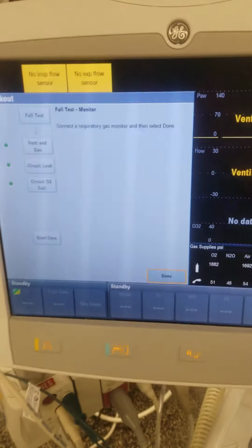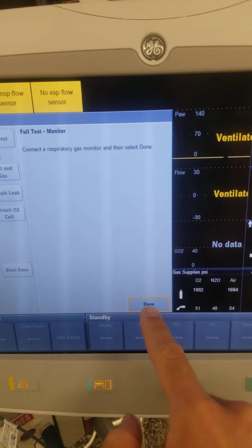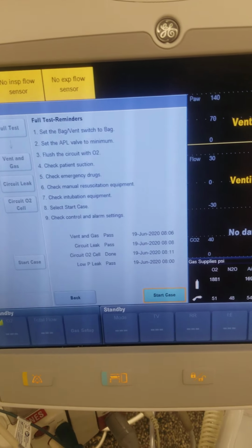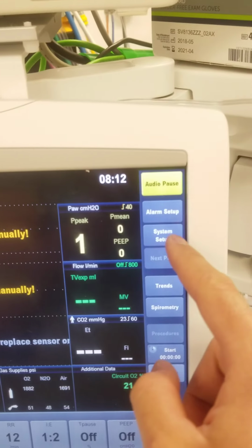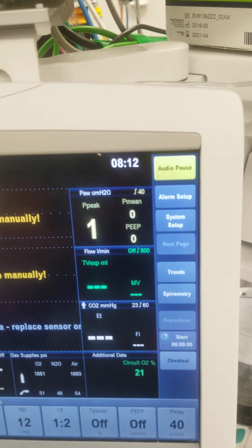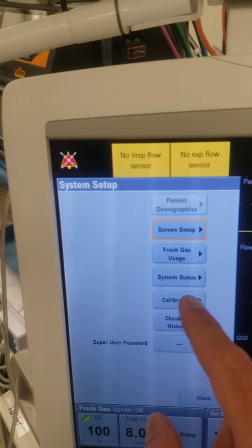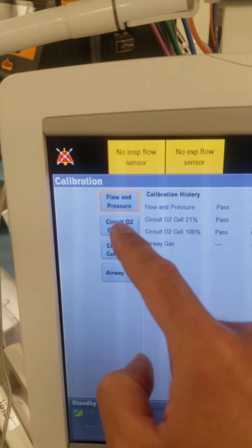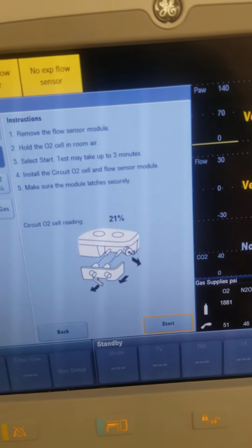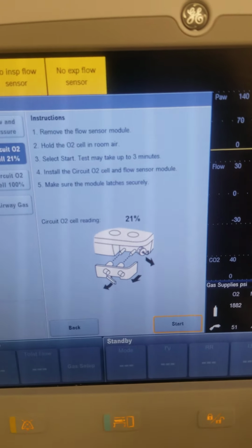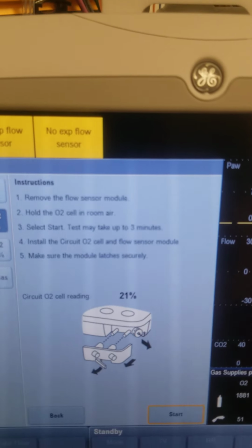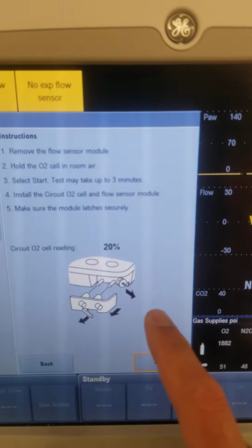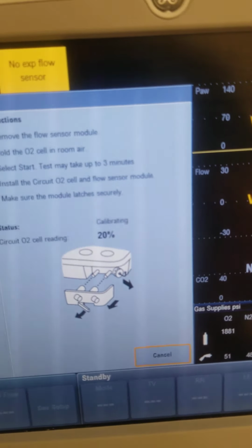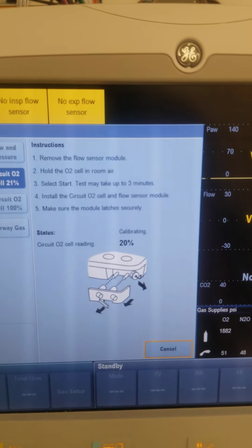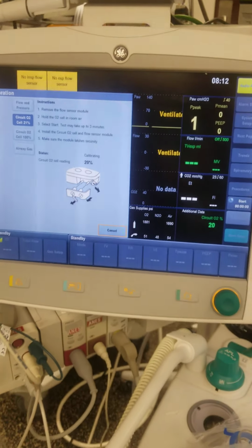Next thing you're going to do is say done. In order to get to the screen, say done again. I usually have to say start case. So now system setup becomes an option. You click on system setup, you go to calibration, and you want to check circuit O2 cell. It's telling you it's reading 21, so it's accurate. But you know what? Let's just do the test, okay? Let's just recalibrate it. Because let's pretend, oh, it's saying 21, so let's pretend it says 18. We're going to hit start, and that's it. It starts calibrating the O2 sensor. So we just fixed a problem that we might have all come across.